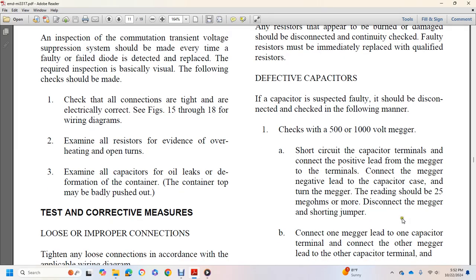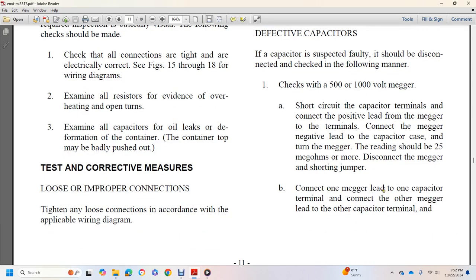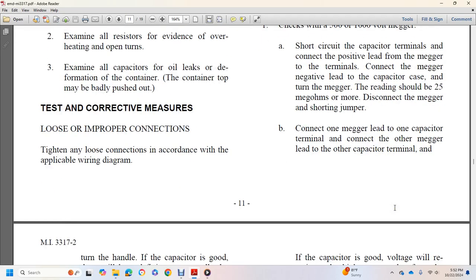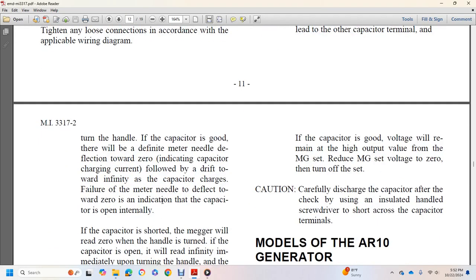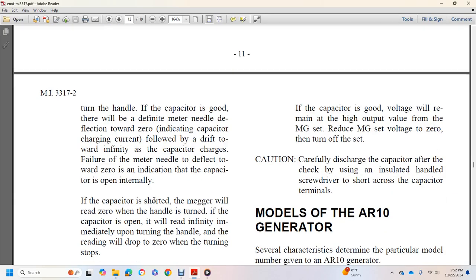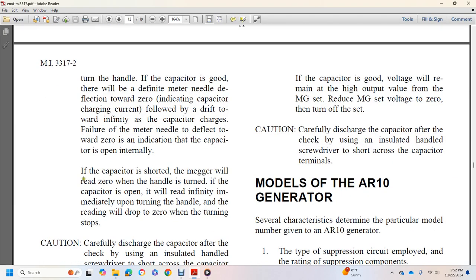megohms or more. Disconnect the megger and the shorting jumper. B. Connect one megger lead to one capacitor terminal. Connect the other megger lead to the other capacitor terminal, and turn the handle. A good capacitor is indicated by the meter needle deflecting toward 0, indicating capacitor charge and current flow, then moving toward infinity as the capacitor charges. Failure of the meter needle to deflect toward 0 is an indication of an open internal capacitor. A shorted capacitor will read 0 when the handle is turned. If the capacitor is open, it will read infinity immediately upon turning the handle, and the reading drops to 0 when the turning stops.